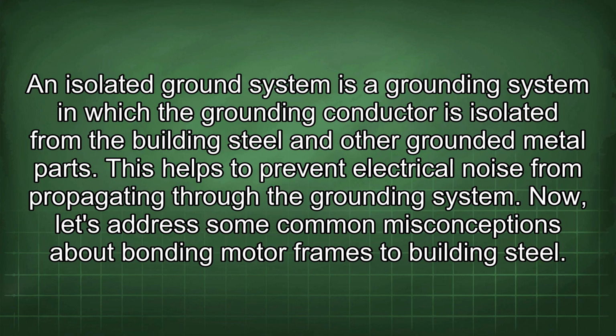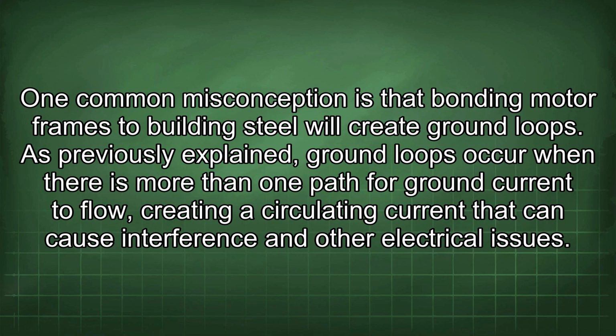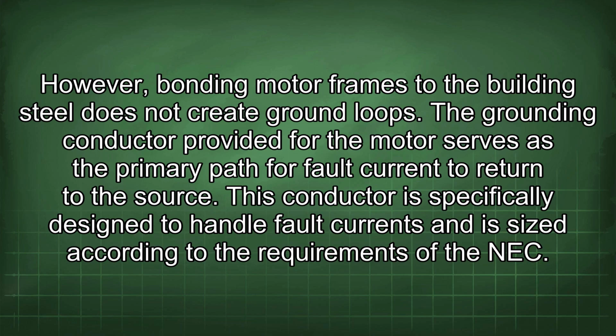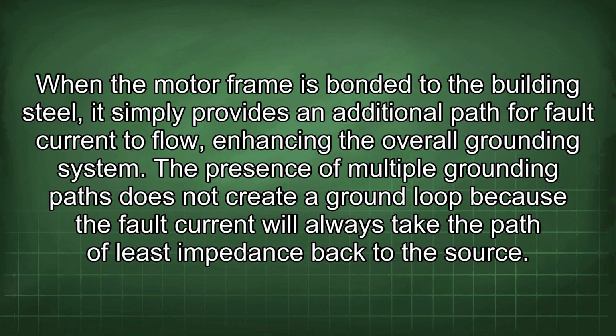Now, let's address some common misconceptions about bonding motor frames to building steel. One common misconception is that bonding motor frames to building steel will create ground loops. As previously explained, ground loops occur when there is more than one path for ground current to flow, creating a circulating current that can cause interference and other electrical issues. However, bonding motor frames to the building steel does not create ground loops. The grounding conductor provided for the motor serves as the primary path for fault current to return to the source. This conductor is specifically designed to handle fault currents and is sized according to the requirements of the NEC. When the motor frame is bonded to the building steel, it simply provides an additional path for fault current to flow, enhancing the overall grounding system. The presence of multiple grounding paths does not create a ground loop because the fault current will always take the path of least impedance back to the source.